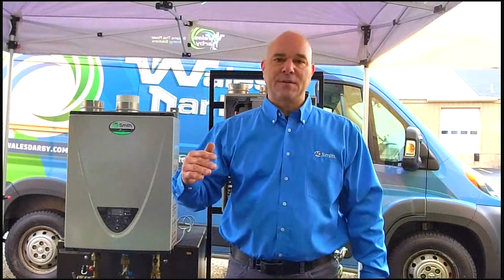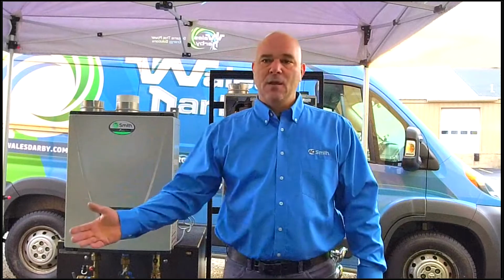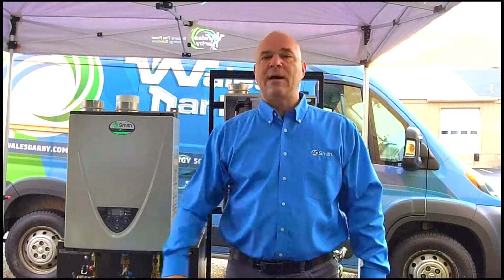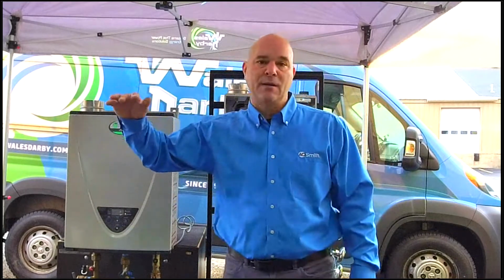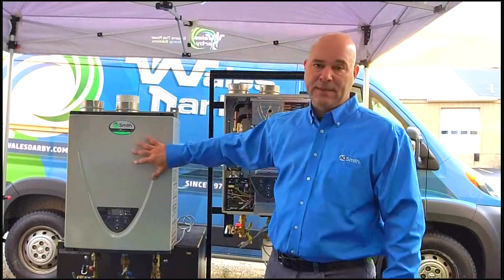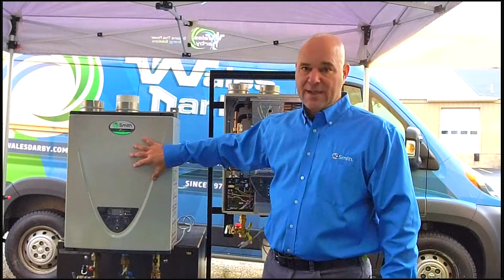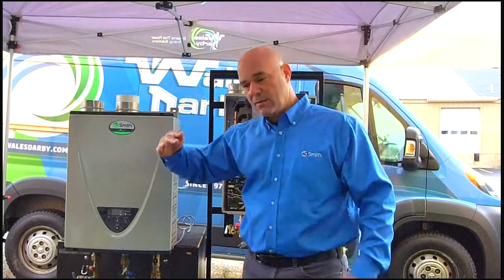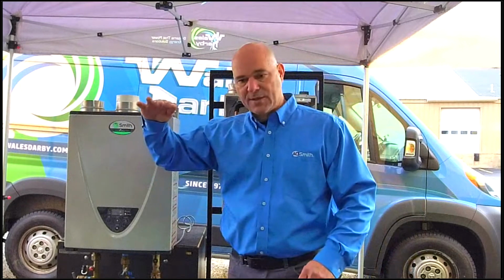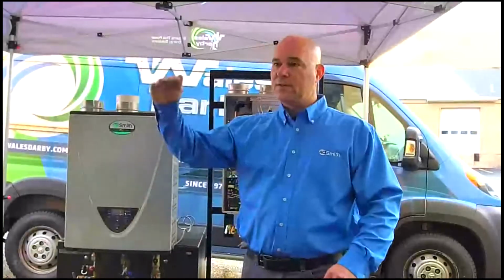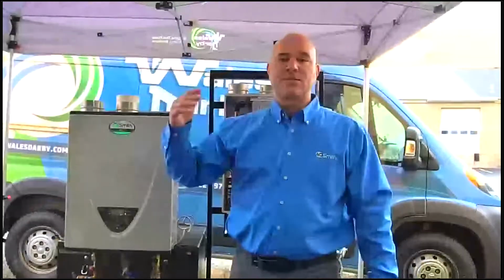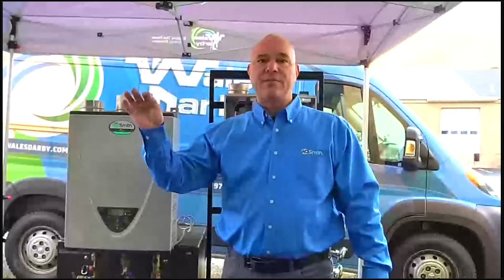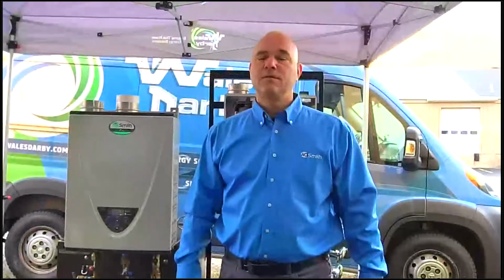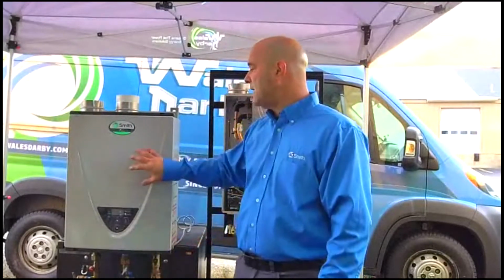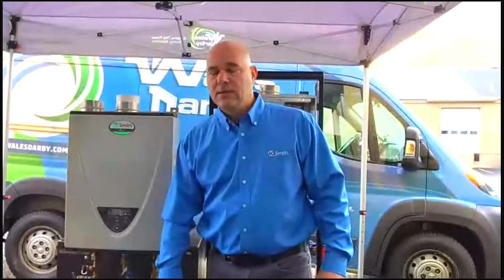And that's at a 70-degree rise. So if I have warmer water in the summer coming out, obviously my flow rates are going to go up higher. These are rated at 10 gallons a minute with a 30-degree rise. So as we get higher elevation of water temperature, we've got to go from 40 to 120. That's when we start to see those 5-gallon, 5.4 flow rates. CT199 will give us the same performance.